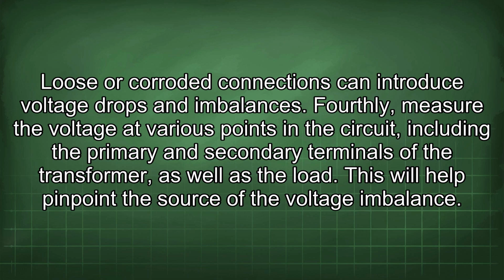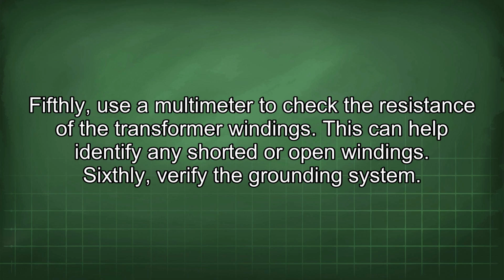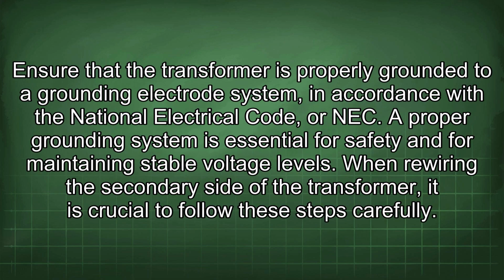Fourthly, measure the voltage at various points in the circuit, including the primary and secondary terminals of the transformer, as well as the load. This will help pinpoint the source of the voltage imbalance. Fifthly, use a multimeter to check the resistance of the transformer windings. This can help identify any shorted or open windings. Sixthly, verify the grounding system. Ensure that the transformer is properly grounded to a grounding electrode system in accordance with the National Electrical Code, or NEC.